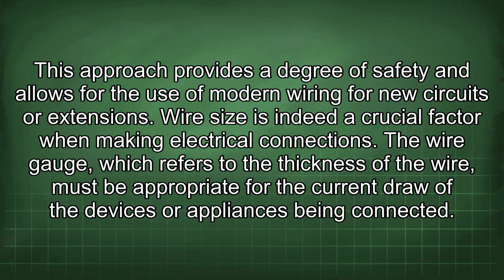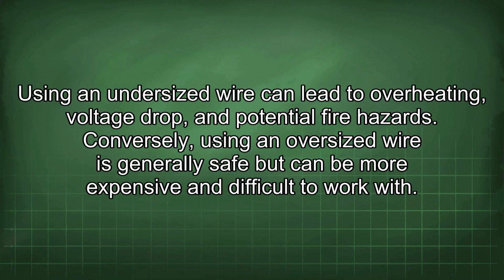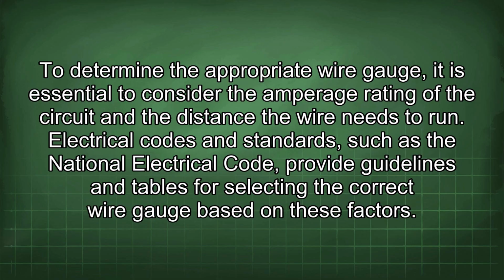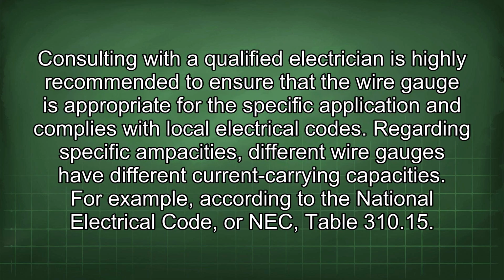Wire size is indeed a crucial factor when making electrical connections. The wire gauge, which refers to the thickness of the wire, must be appropriate for the current draw of the devices or appliances being connected. Using an undersized wire can lead to overheating, voltage drop, and potential fire hazards. Conversely, using an oversized wire is generally safe but can be more expensive and difficult to work with. To determine the appropriate wire gauge, it is essential to consider the amperage rating of the circuit and the distance the wire needs to run. Electrical codes and standards such as the National Electrical Code provide guidelines and tables for selecting the correct wire gauge based on these factors. Consulting with a qualified electrician is highly recommended to ensure that the wire gauge is appropriate for the specific application and complies with local electrical codes.